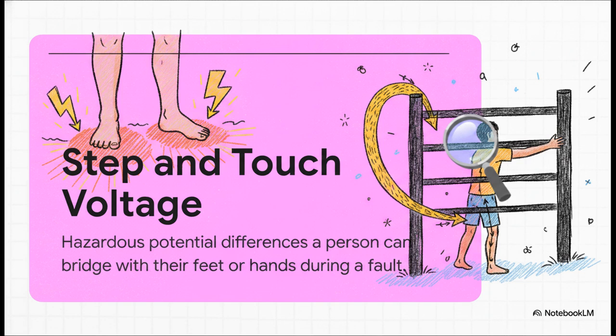So here's the crucial point. Ground potential rise itself isn't what kills you. It's the difference in potential across your body that does. If you take a step and one foot is on soil at 5,000 volts and your other foot is on soil at 4,000 volts, well, that 1,000 volts of potential difference is going to travel right up one leg and down the other. That is called step voltage. If you touch a grounded metal fence while standing on charged soil, that potential difference travels through your arm and down your legs. That's touch voltage.